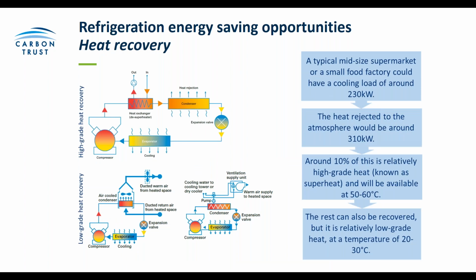Moving on to heat recovery. So heat recovery is a really useful way of making use of the latent heat that is dumped by a refrigeration system. So in a system, thermal energy that's collected from one space and delivered to another is essentially dumped externally and not used again, but you can actually recover heat from the system. So there are two types, high grade and low grade heat. You can see that the high grade heat that you can recover is at around 50 or 60 degrees Celsius, and that the low grade heat is around 20 to 30 degrees. So you can use both of these types of heat.